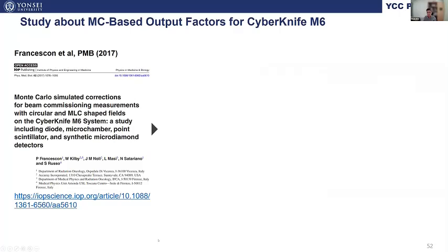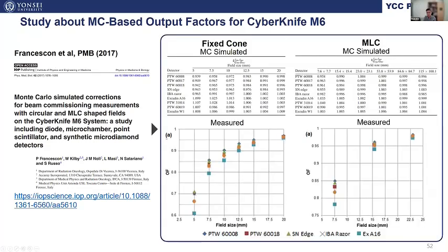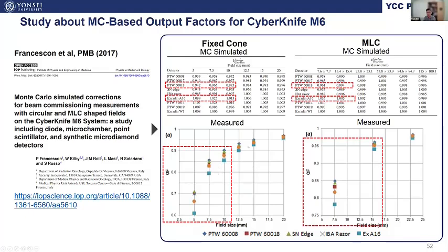And there is a very informative publication that can clearly answer this complication, published in PMB in 2017. They revealed the discrepancies across the different detectors in small field dosimetry of CyberKnife, as being demonstrated by both Monte Carlo and actual measurements. Interestingly, A16 ion chamber was found to be kind of outlier, yielding the biggest difference compared to the other detectors, especially in very small field. This strongly recommends adjusting the output factors when we use A16 ion chamber for patient-specific QA. In the beam commissioning process, we measure the output factors for both A16 and SRS diode chambers, which have been reflected in analyzing the results of patient-specific QA so far.